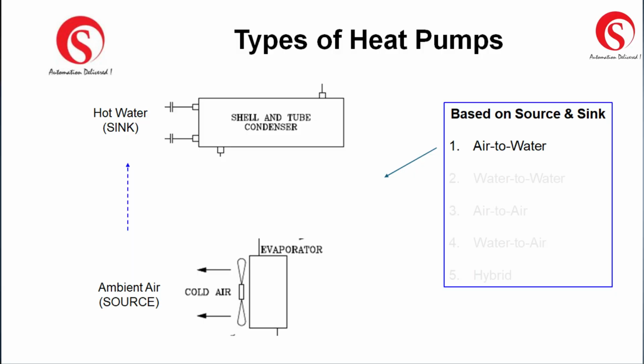Good. In today's episode, we are going to discuss how a typical air to water, 80 degrees centigrade industrial hot water heat pump works, and what the parameters are, what kind of COP we get, etc. Let me start. So, taking a 500 liter tank that we want to heat up to 80 degrees centigrade, it's a standard air to water standalone heat pump. So we are taking atmospheric air.